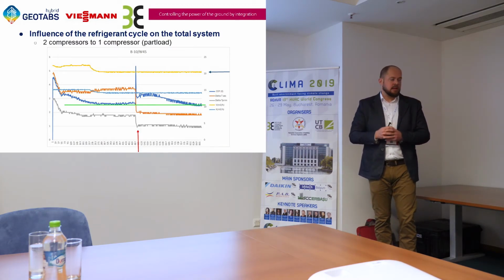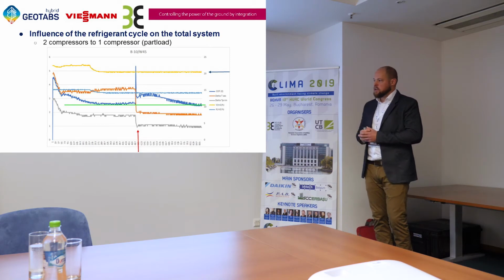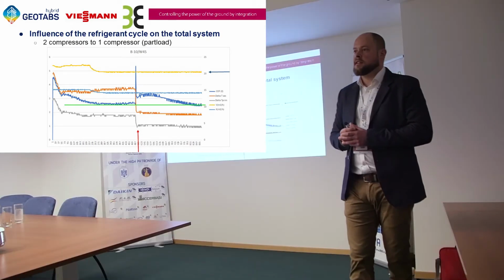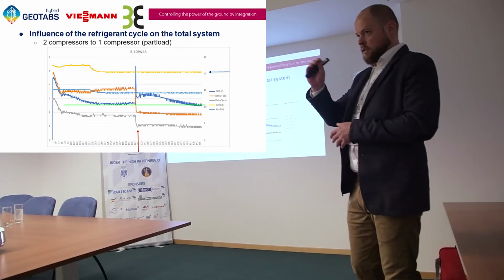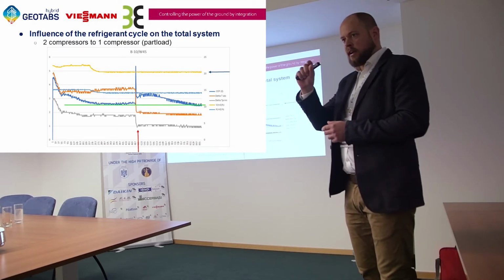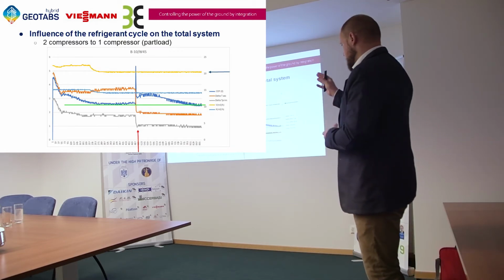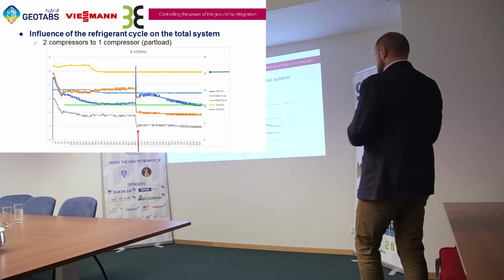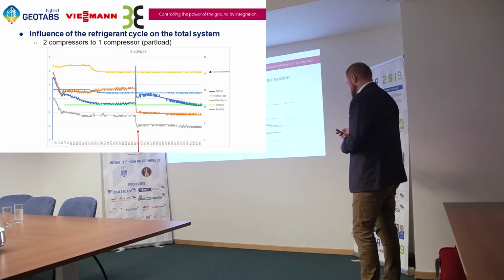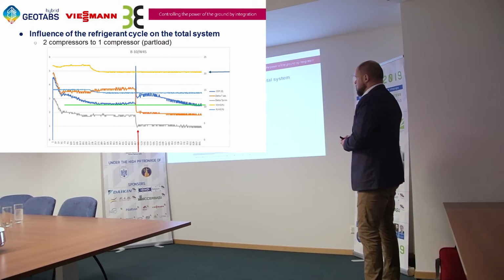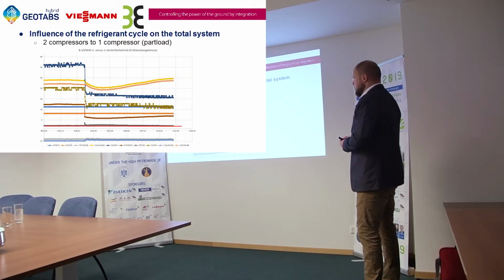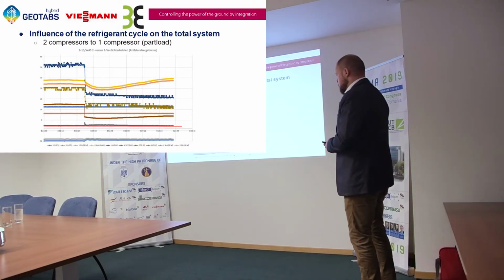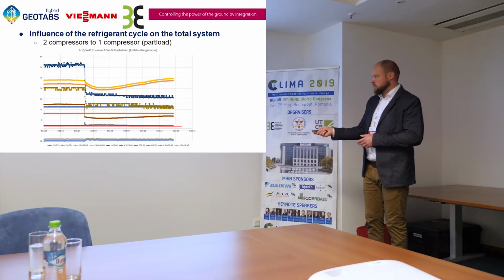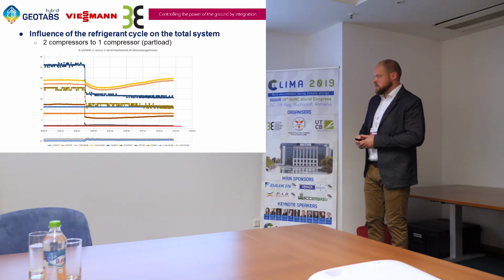So it will stabilize, and a part of the explanation here is that we have a fixed superheat. The expansion valve is regulated on a fixed superheat, and that's part of the explanation why the COP doesn't change that much. So this is another example where you can see the part load, and you can also see that when switching from 2 compressors to 1 compressor, in time it will be about the same COP.